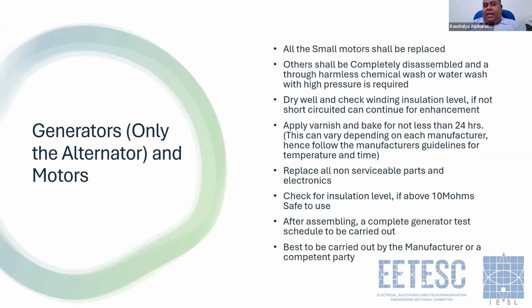Generators. In this case, we are only talking about the alternator, which is related to electrical, and motors. Small motors, forget them, replace them. Others shall be completely disassembled, and a thorough, harmless chemical wash or high-pressure water wash is required, because you have to remove all the mud and stain inside your motor or the alternator. You have to thoroughly wash them. Then you will have to dry them well. After drying completely, check the insulation level.